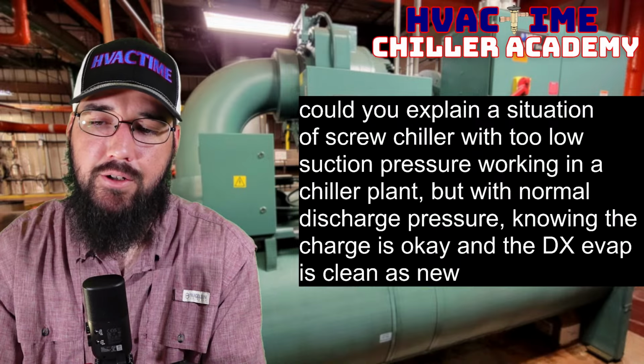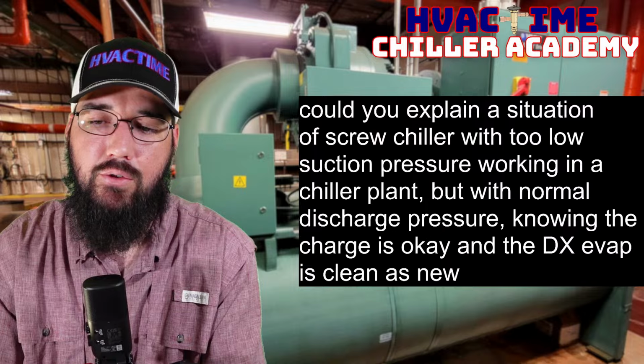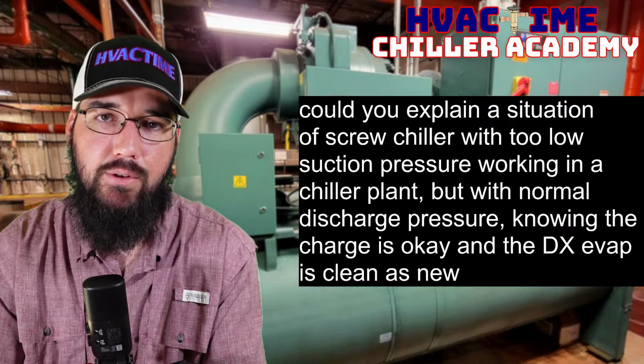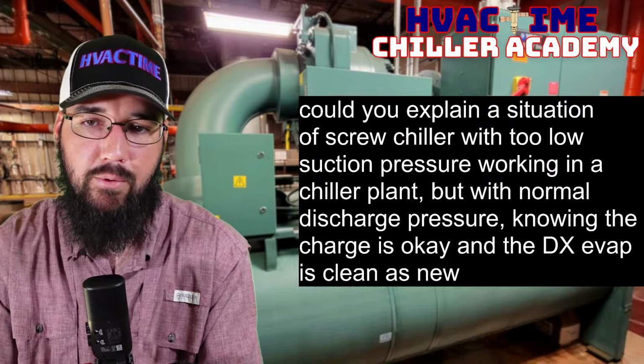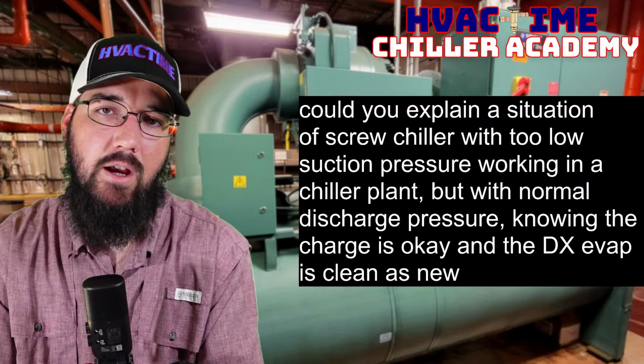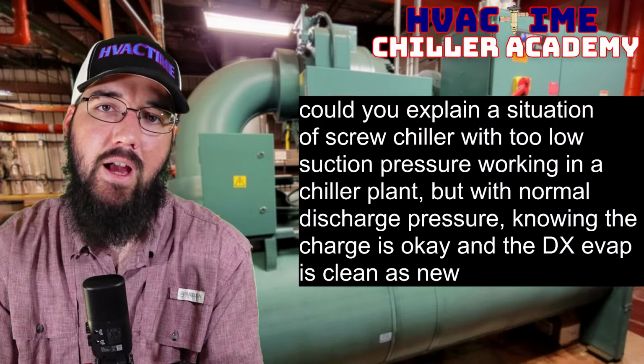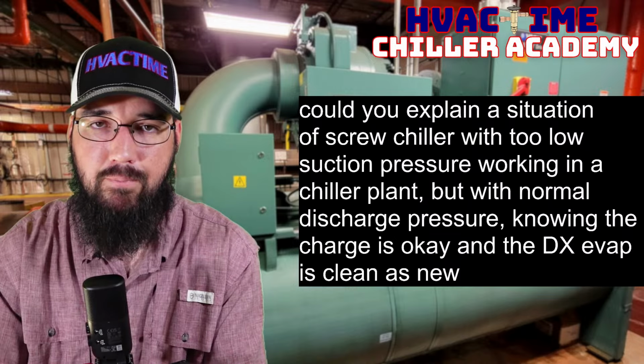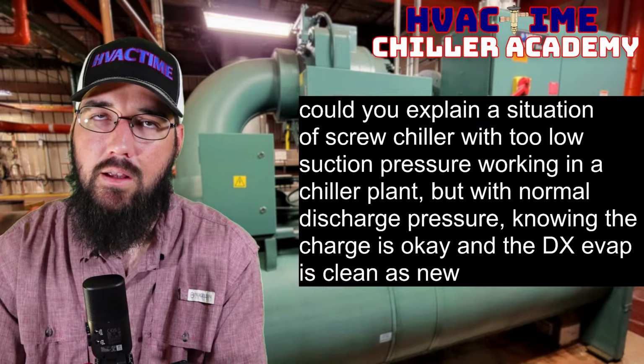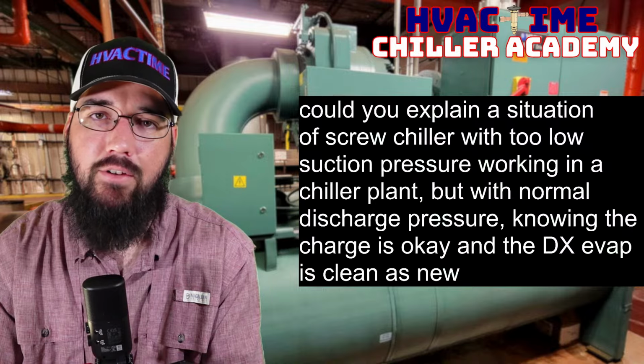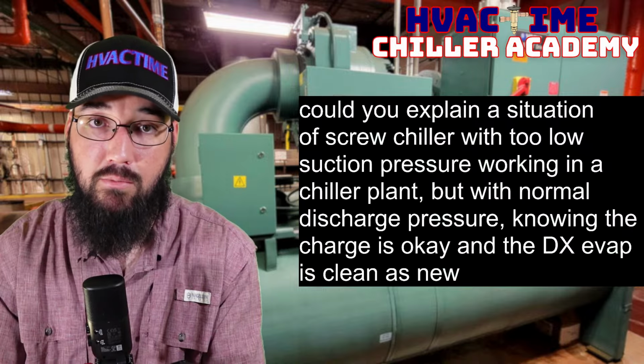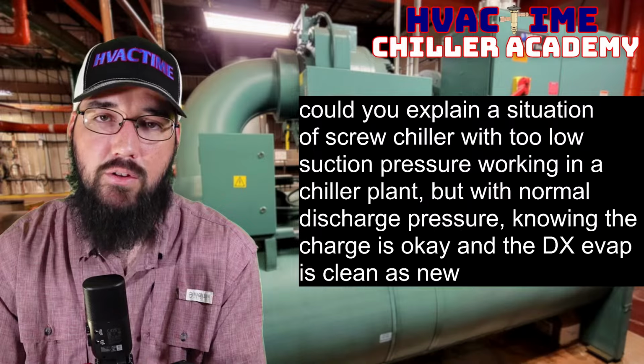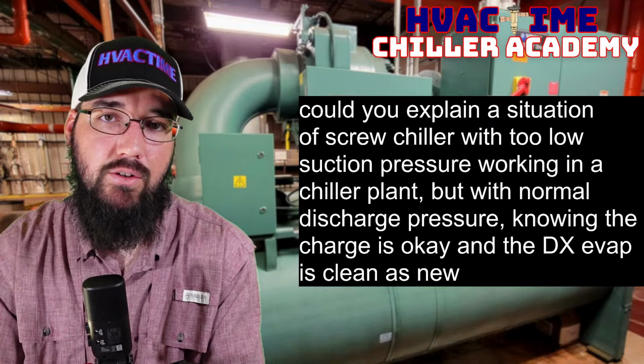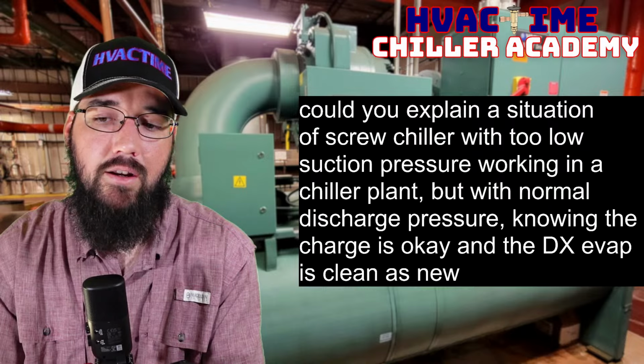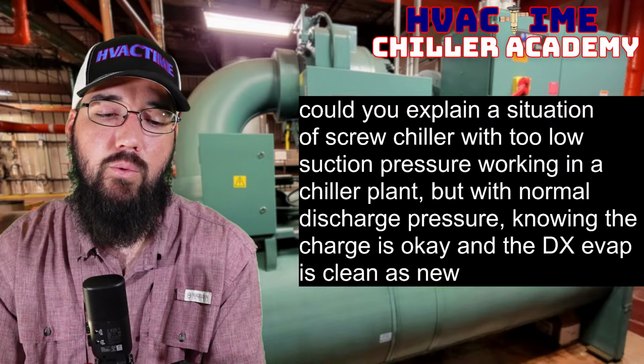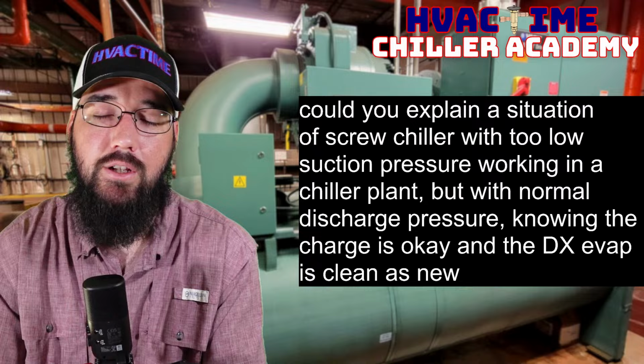The discharge pressure responds directly to the amount of heat being inputted into the evaporator. So the more heat the evaporator is taking in, the higher the discharge pressure will be. So just, even though you're having a low suction pressure at this moment, you're still making set point, which means you're still taking in enough heat to hit set point leaving the machine.